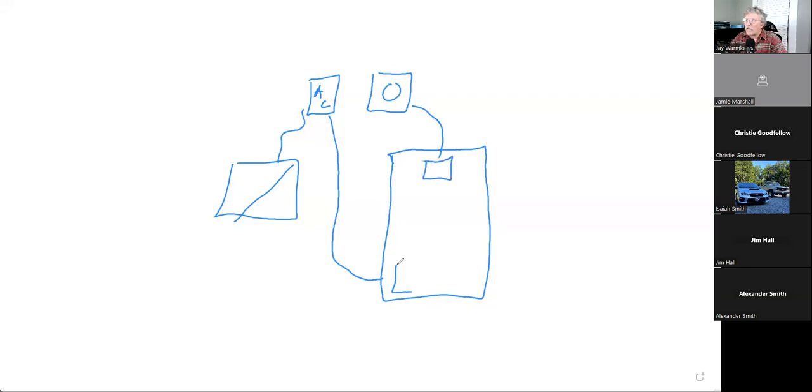And we're going to hook into a double pole breaker here. So this is the last part of the system. This is the inverter output circuit of a standard grid tied system. All right. So this would be referred to as a load side connection because our connection point of our system is on the load side of the main disconnect. And in here, this is your main disconnect, this breaker that's connected to the meter.